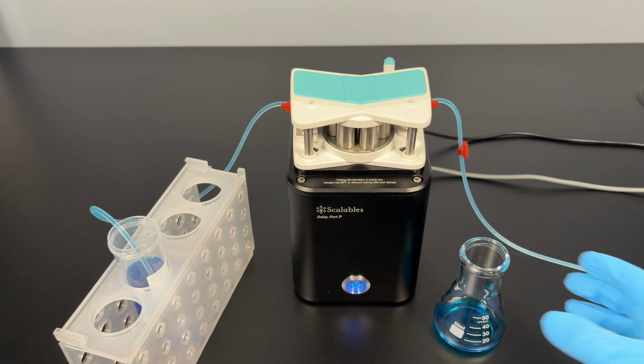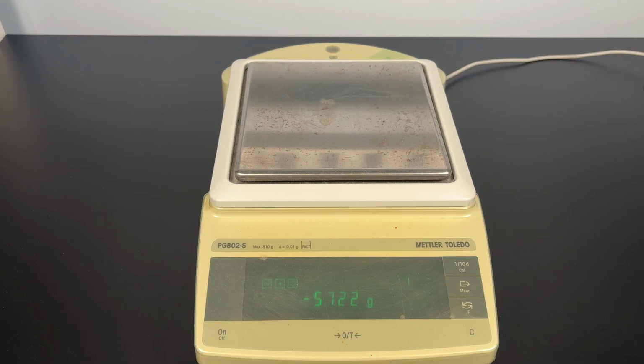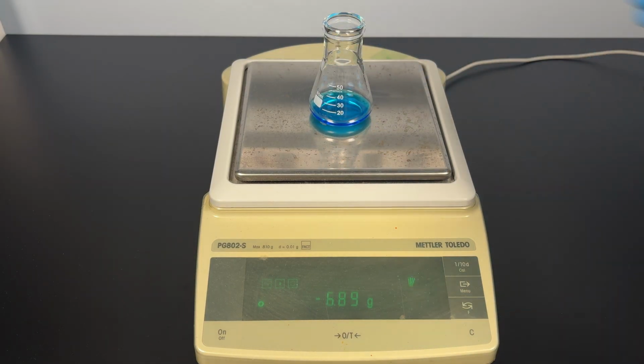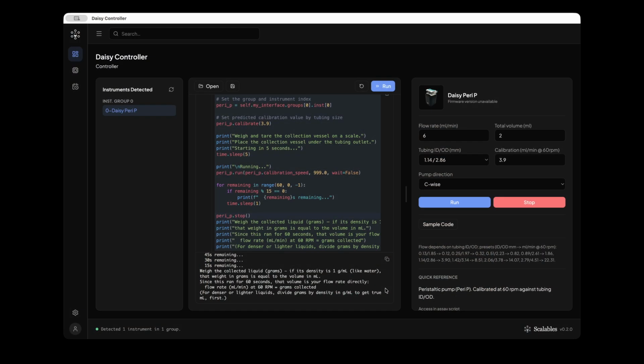Then weigh the collection vessel with the liquid dispensed. Here we collected 4.04 grams of liquid. Measuring the volume dispensed in 60 seconds gives the calibration value in mL per minute at 60 RPM, depending on the density of the liquid.